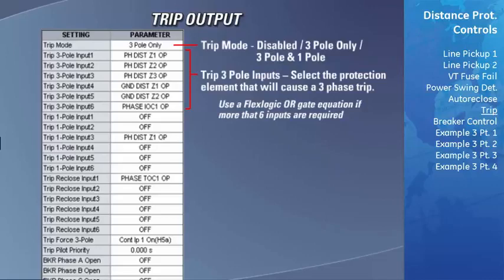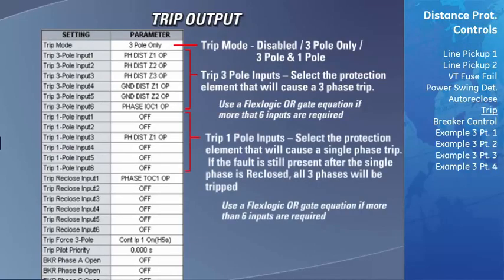In the next 6 fields that are labeled Trip 3-pole Inputs 1 to 6, you need to enter all of the protection element output operands that you wish to cause a 3-phase trip when they detect a fault. If you require the ability of selecting more than 6 inputs to cause a 3-phase trip, you will need to create a FlexLogic equation where all of those additional inputs will be ORed together and then assign that virtual output to this list.